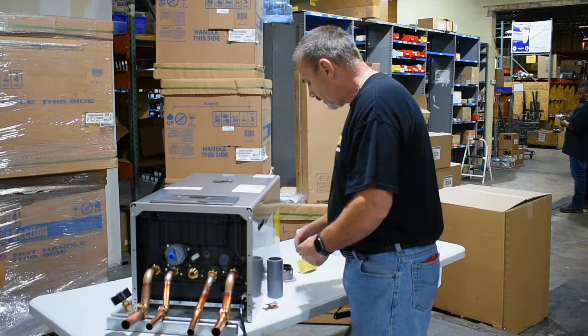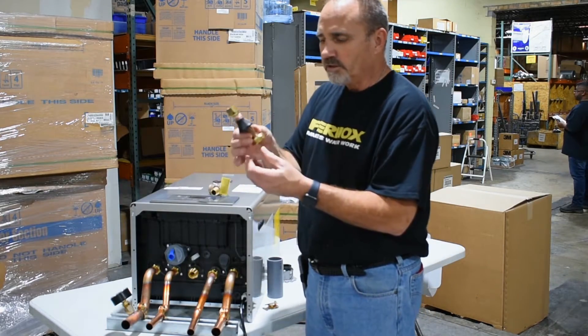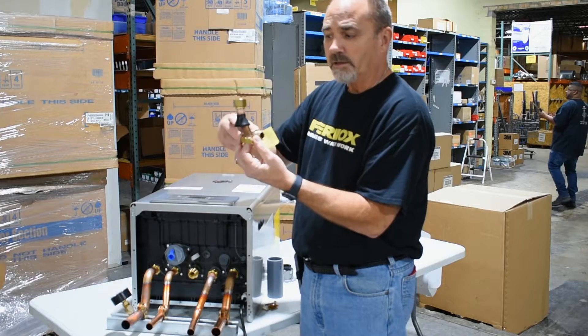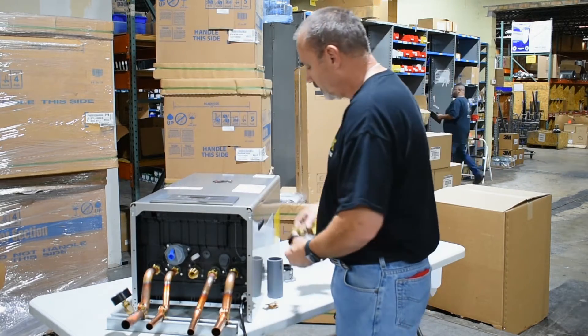Next up, the pressure relief valve. They give you everything you need. This goes off the top of the unit and you'll see there's a little knockout. This spins on to the top of the boiler, and then once it's through the hole, this rubber grommet seals the hole, and then you can put in your pressure relief valve on top — so you're good there.